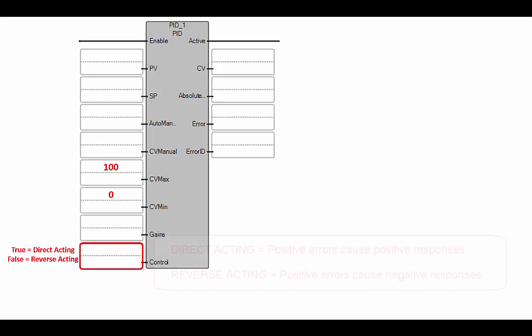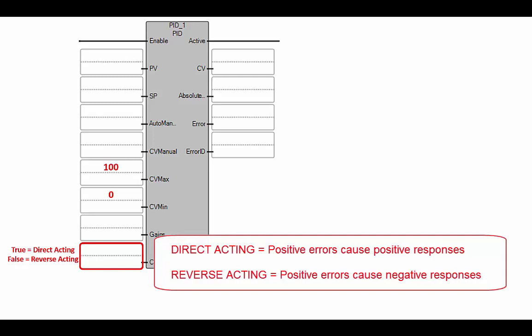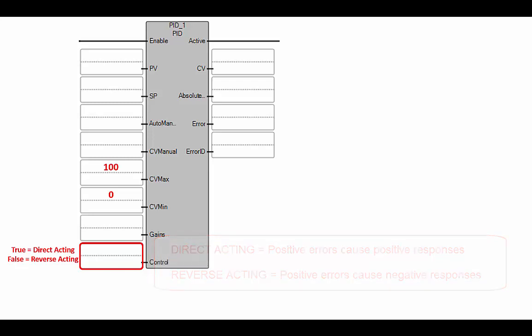This control input, if you remember from the last video, is where we indicate whether this PID is a direct acting or reverse acting controller. A reverse acting controller is one where a positive error — meaning our current tank value is higher than our set point — results in a reduced control variable, meaning we close off the fill valve so the tank level can come back down. That is a reverse acting controller, so we'd set this to false in our case.